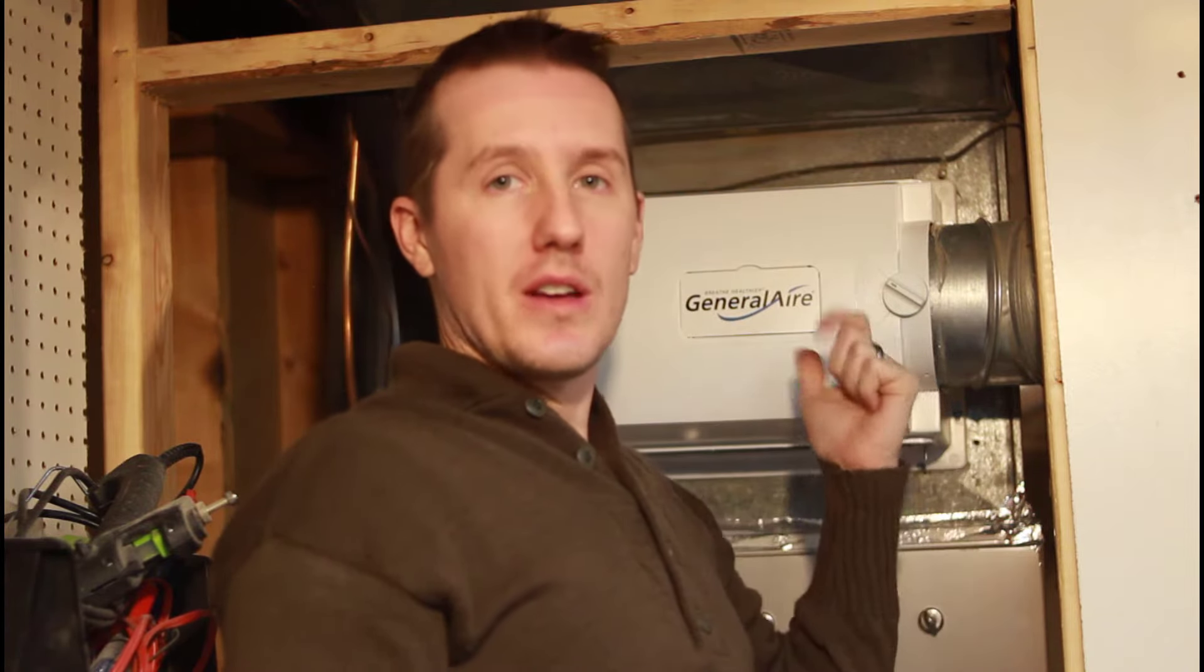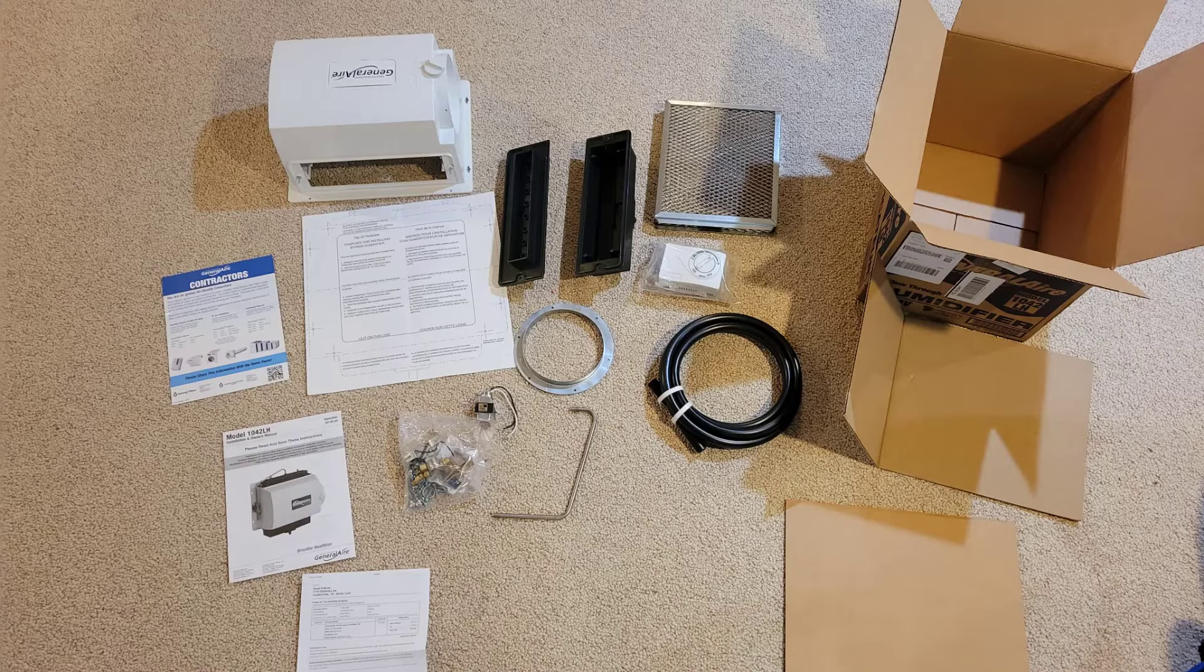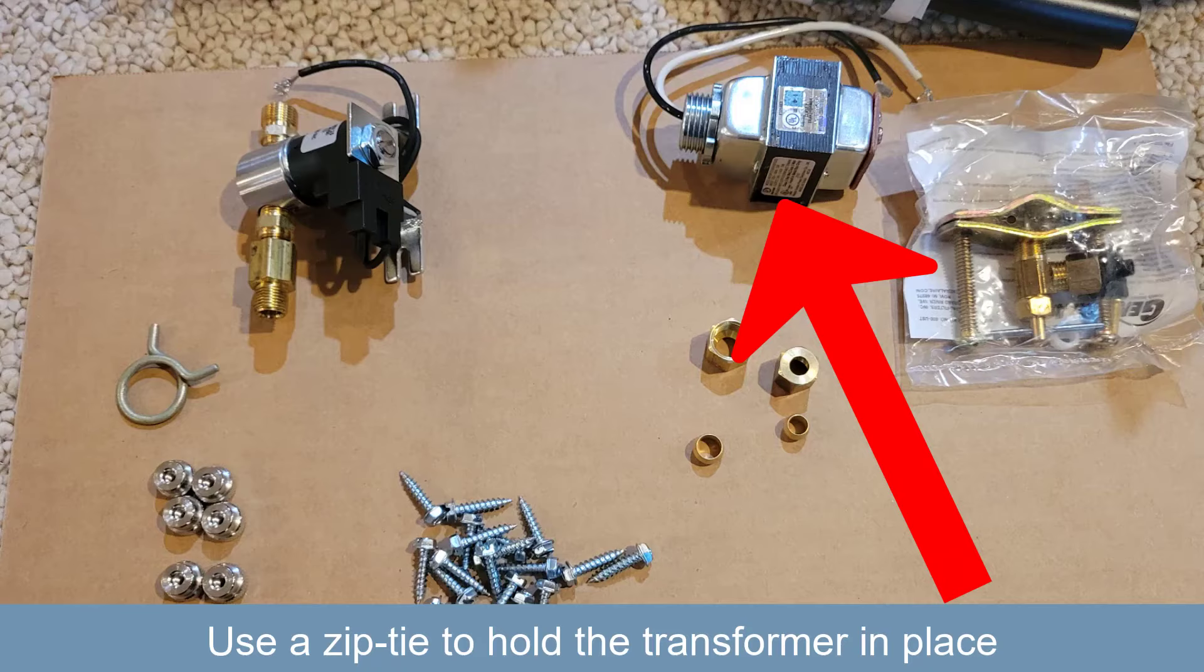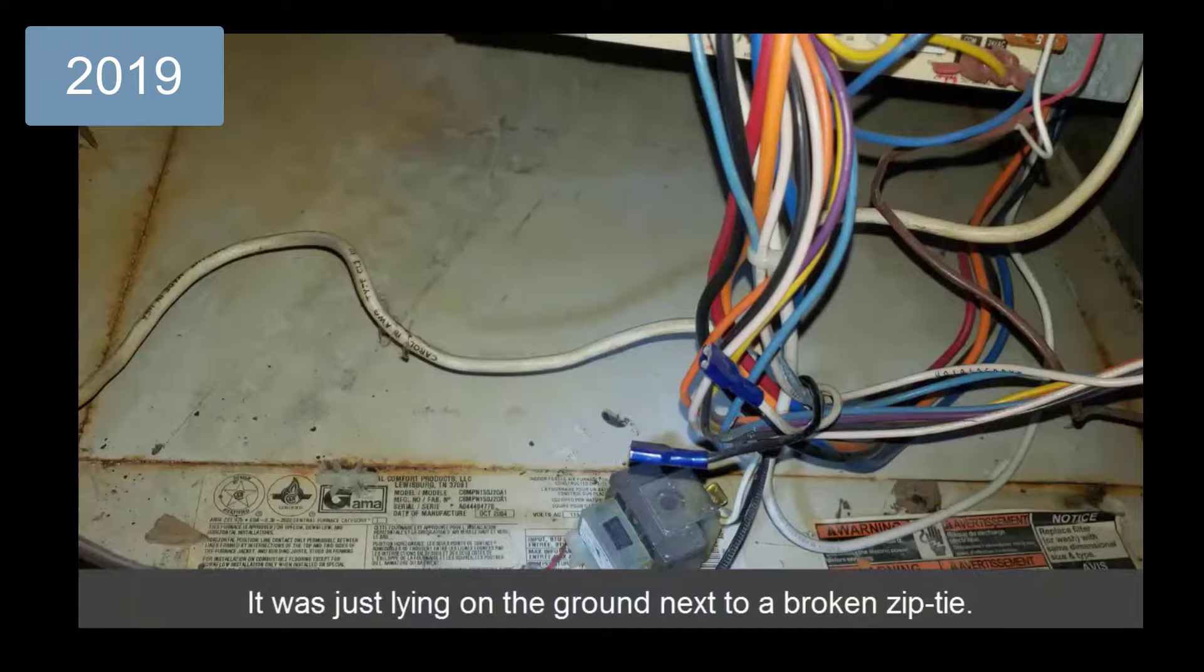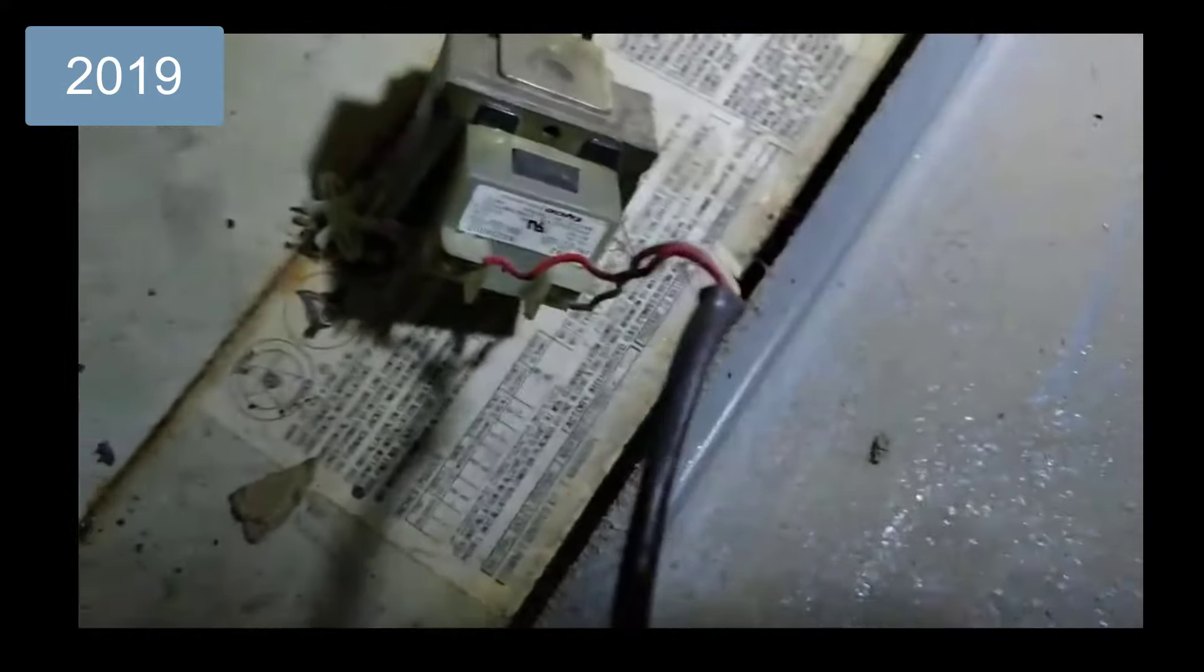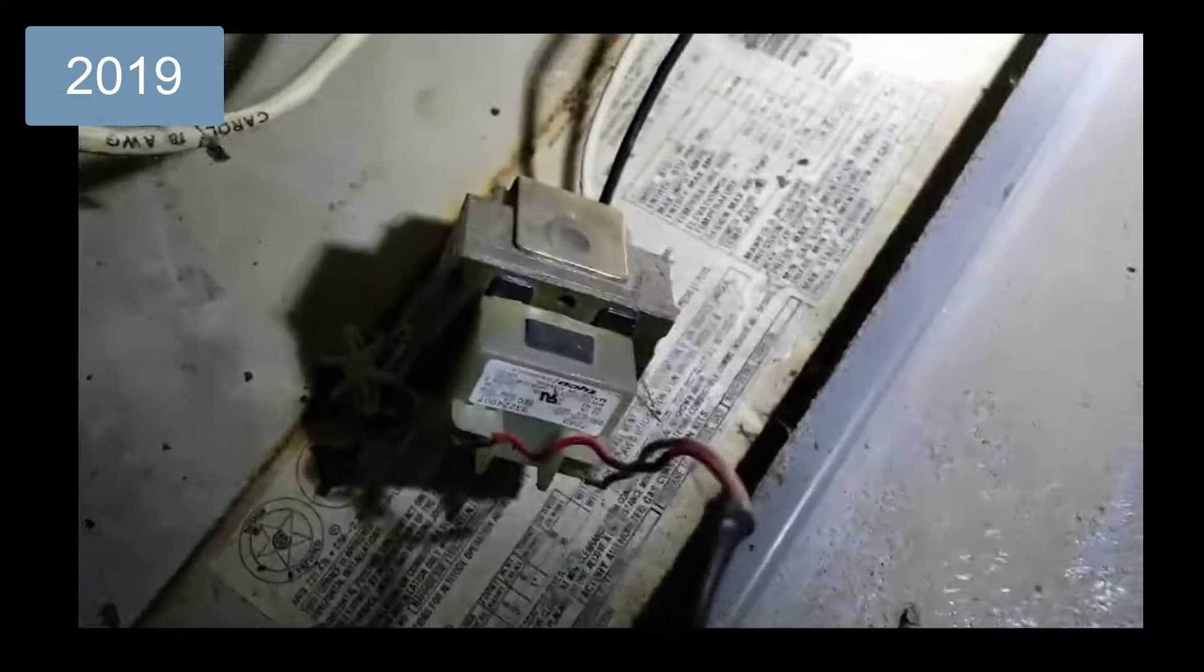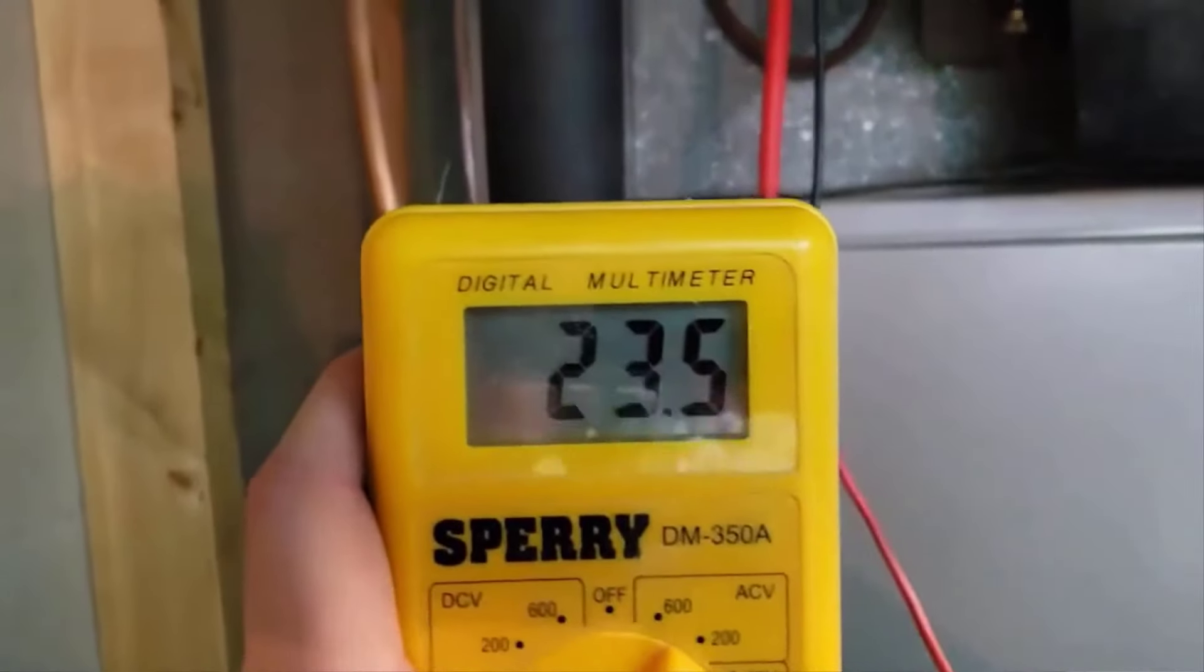Now as far as wiring, if you are doing this new, you are going to have to go back to your circuit board on the furnace and wire in that transformer. One tip is to use a zip tie to hold it in place, because a couple of years ago, my transformer fell off and the wires came unplugged. So make sure that transformer is in there secure, it is pretty heavy. But since mine is already in, I am just going to use the transformer I had. It supplies 24 volts AC. And I am just going to connect it with some wire connectors to the solenoid.